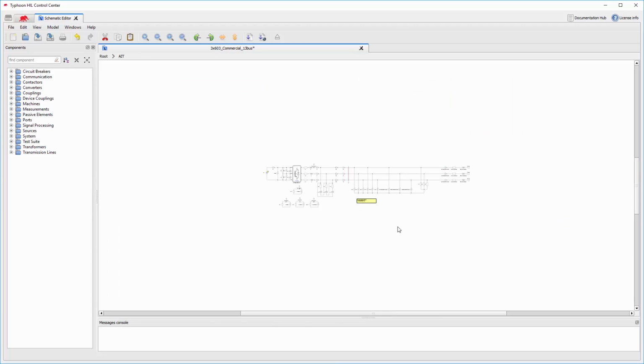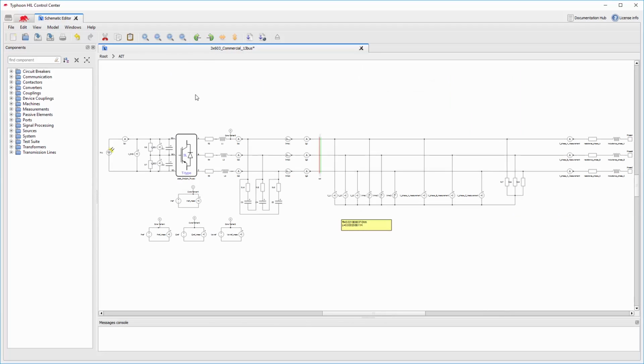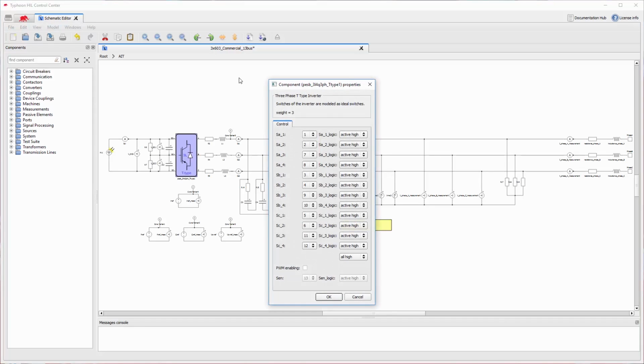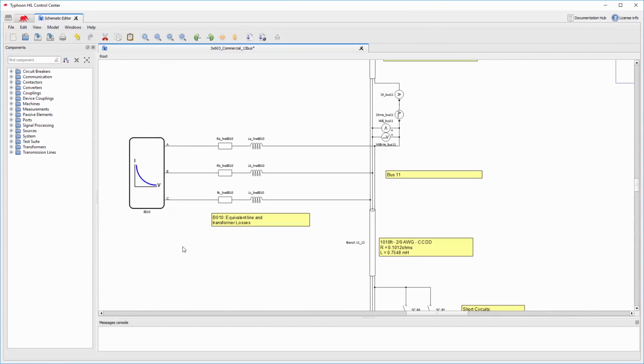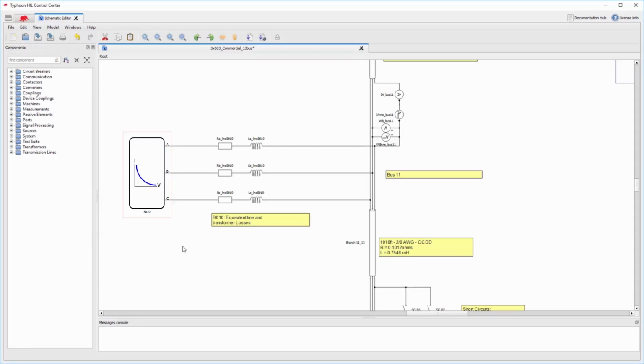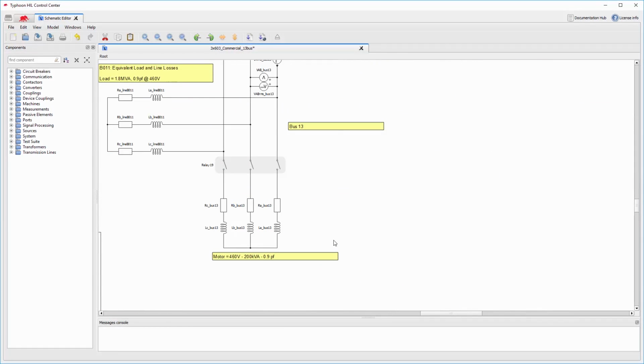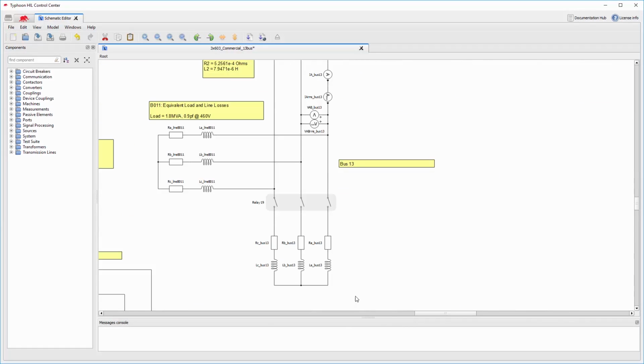The PV inverters are both three-phase, three-level inverters that use the maximum power point tracking algorithm known as MPPT. The PV inverter controllers receive information measured at the point of connection to the grid and send commands to the inverter block. In this block, you can define which channels will be used to receive commands. Dynamic loads are represented by constant power load elements from our library that can have their set points changed during simulation. Passive loads are represented by resistors, inductors, and capacitors.